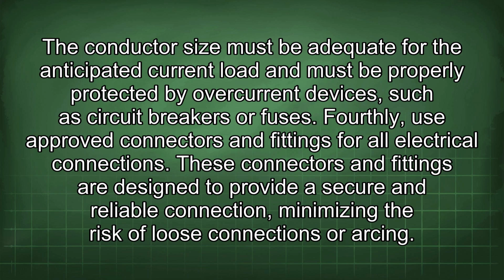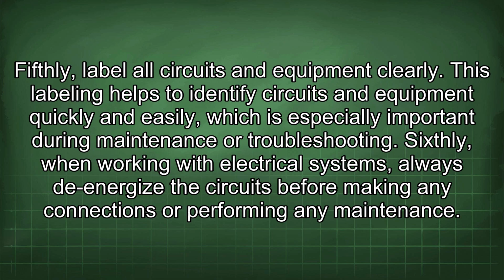Fourthly, use approved connectors and fittings for all electrical connections. These connectors and fittings are designed to provide a secure and reliable connection, minimizing the risk of loose connections or arcing. Fifthly, label all circuits and equipment clearly. This labeling helps to identify circuits and equipment quickly and easily, which is especially important during maintenance or troubleshooting.